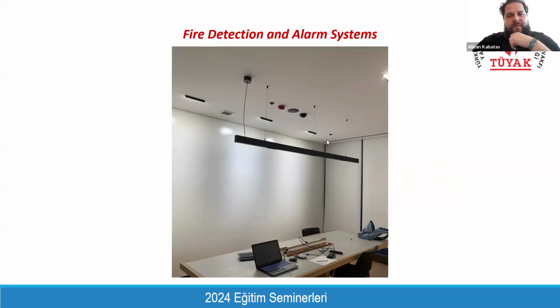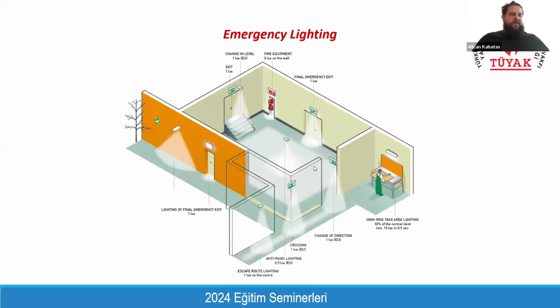since we don't have 1 meter parapet in the facade of our building, we have a closely located facade protection sprinkler as well. Even if we don't need it by distance, it is provided because of Turkish fire code requirements. And also we have emergency lighting. This is a good example to understand main principle of the emergency lighting. The exit routes and the fire and life safety equipments and the main technical rooms should be protected, should be equipped with emergency lighting system so that in case of any kind of energy loss, these areas can be found by occupants and egress can be done safely.